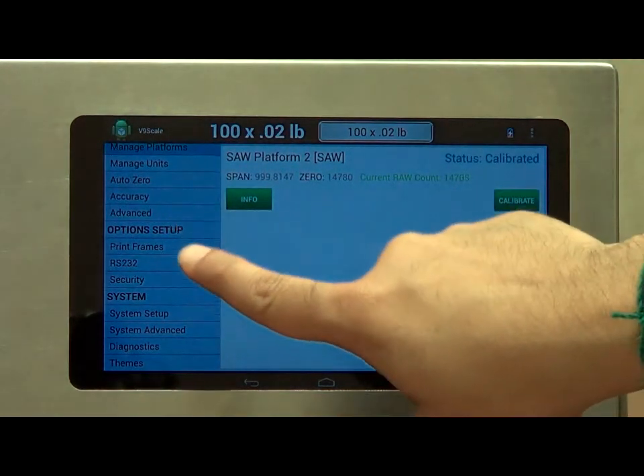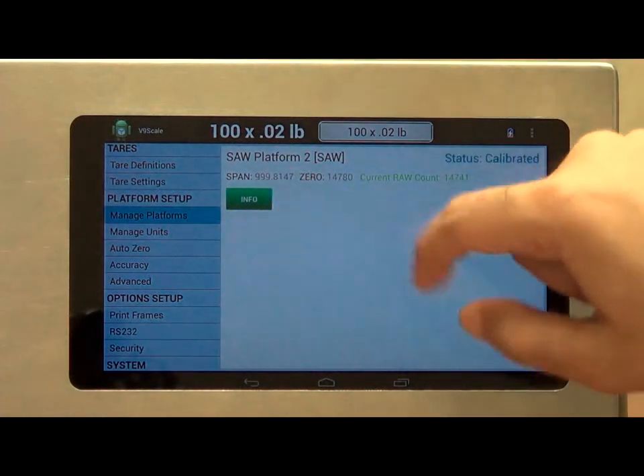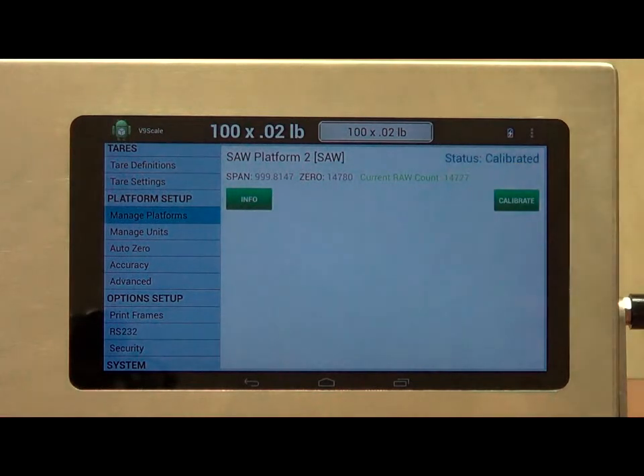In this screen, we can look at the status of the current platform. We see the calibrated span, the calibrated zero, and the current raw count. We know the scale is working fine if we see this raw count moving.